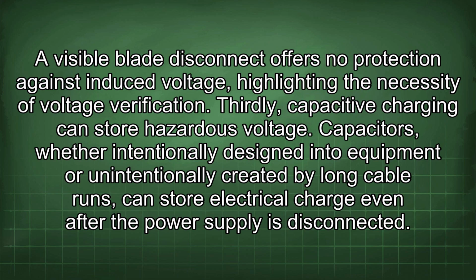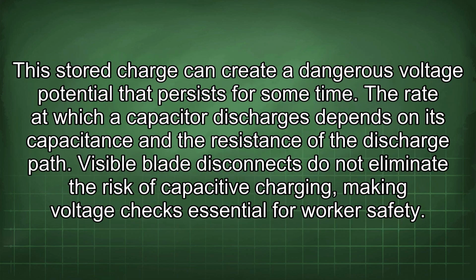Thirdly, capacitive charging can store hazardous voltage. Capacitors, whether intentionally designed into equipment or unintentionally created by long cable runs, can store electrical charge even after the power supply is disconnected. This stored charge can create a dangerous voltage potential that persists for some time. The rate at which a capacitor discharges depends on its capacitance and the resistance of the discharge path. Visible blade disconnects do not eliminate the risk of capacitive charging, making voltage checks essential for worker safety.